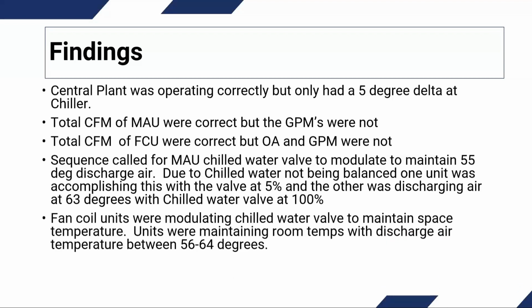The fan coil units, the way the sequence called and the way the sequence was working was for the chill water valves to modulate to maintain space temperatures. We had no problem maintaining space temperature. As we indicated earlier, the average temperature in the building was about 68 degrees. And the majority of the units were maintaining the temperature by modulating the valve and discharging temperatures between 56 and 64 degrees.